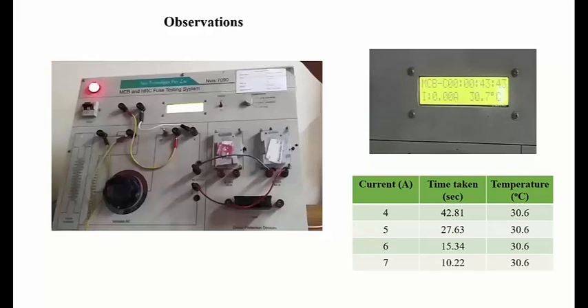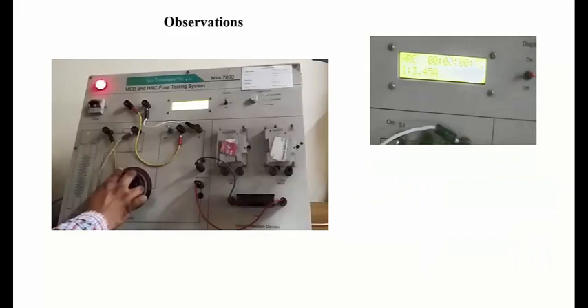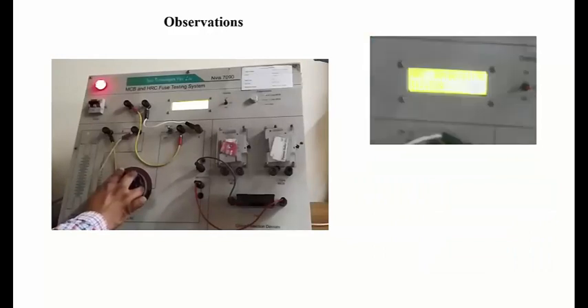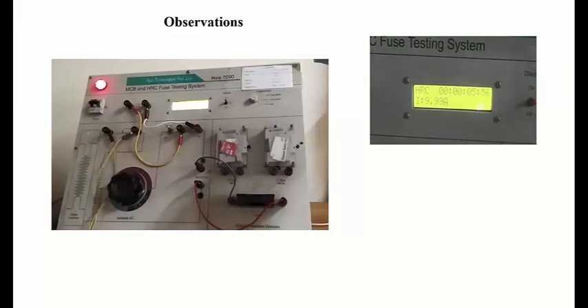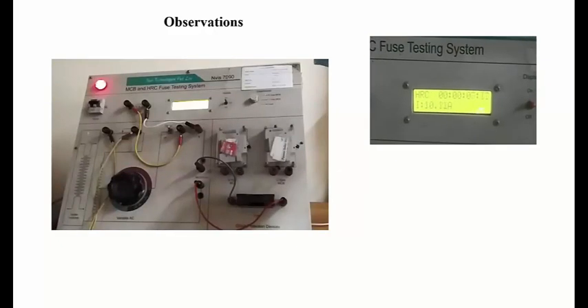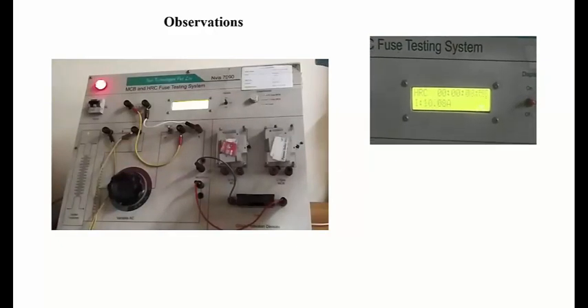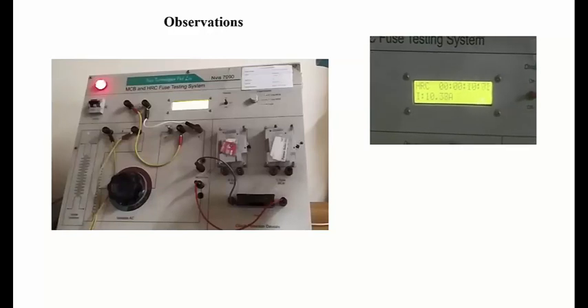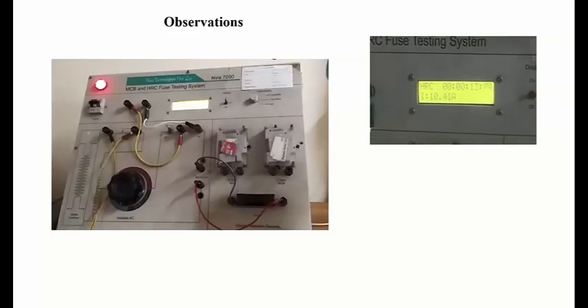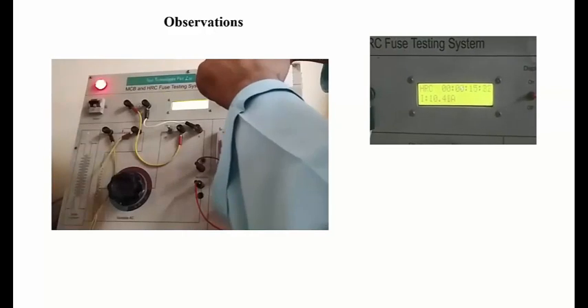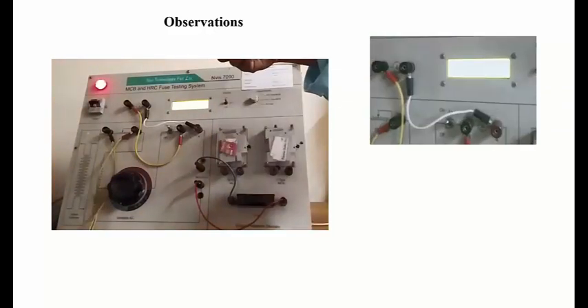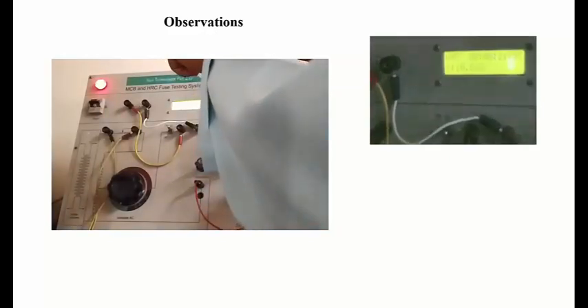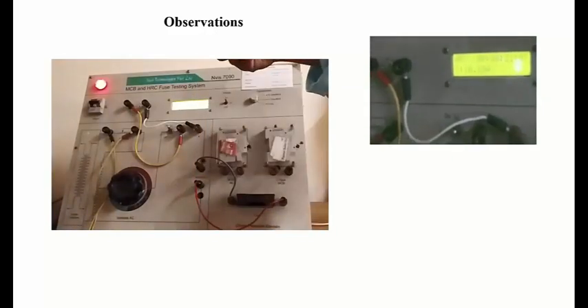We'll be testing the HRC fuse and observing the time that the HRC fuse takes at different values of current. We have connected the terminals to the HRC fuse. In this experiment, since we all know that the fuse can be used only once, the fuse will be blown and will be tripping the circuit, so it cannot be reused.